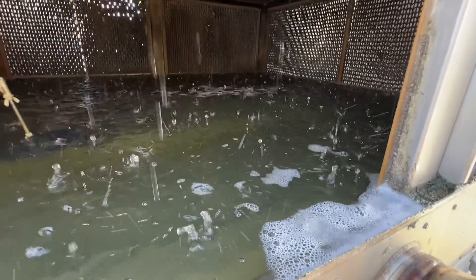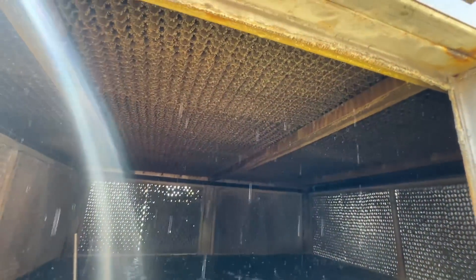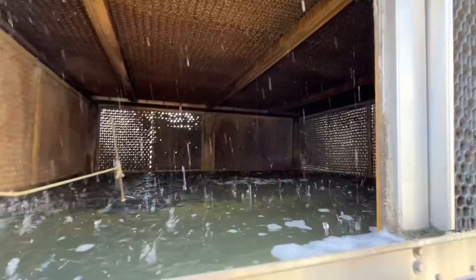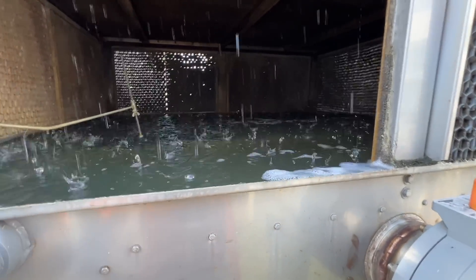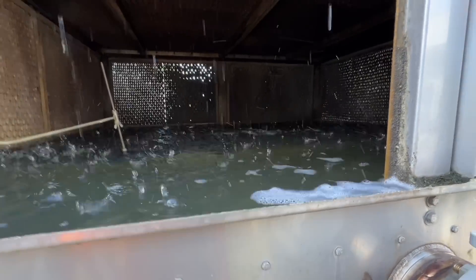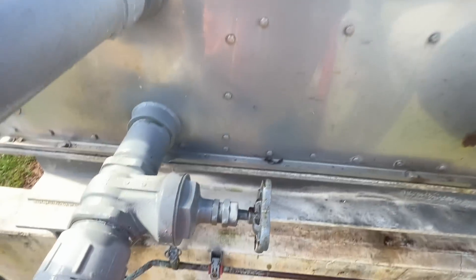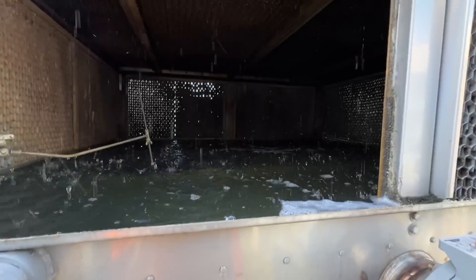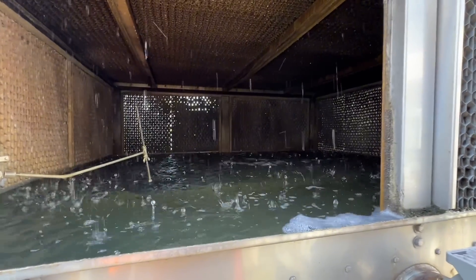I think we got it — it's definitely receding. We're not putting any more water in, maybe dripping less. Maybe we got it right at the cusp there, so we'll save a little bit of water when these things shut down. We'll do one more startup here to watch the sump and make sure it doesn't cavitate.